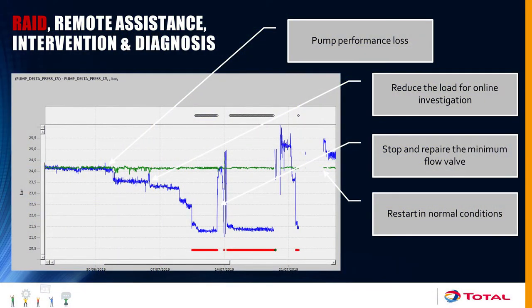Another case shows a step decrease in the performance and efficiency of an engine. This was coming from equipment outside the main package — specifically a minimum flow valve of a heavy-duty water injection pump. This valve is not considered part of the machine directly, and there is not a lot of instrumentation on this kind of valve, so there is no immediate means for an operator to identify a potential failure within it. However, from our analysis and my personal experience having worked on this machine a couple of years ago, I could inform colleagues that it would be good to plan the replacement of this valve as soon as possible.